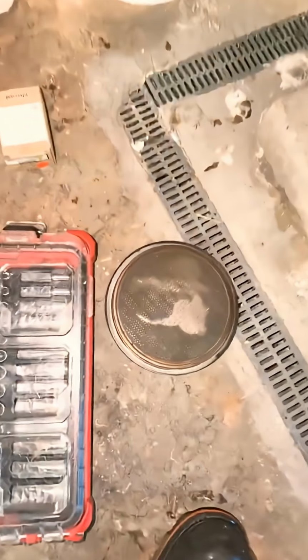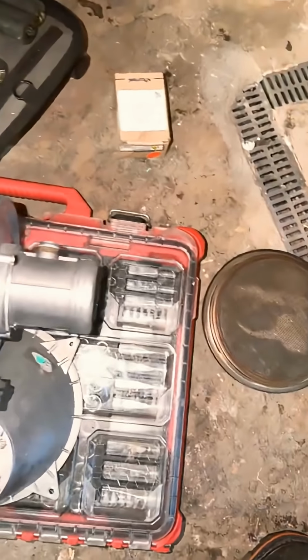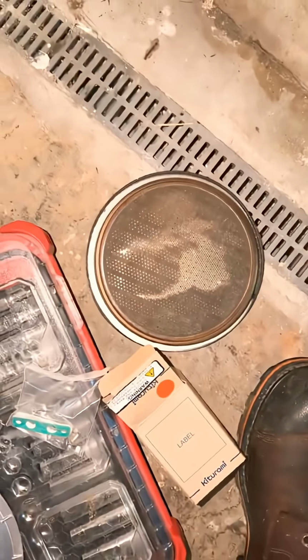But that's why maintenance is important on these. I did not want to put it back together like that. And I also have a new electrode. So these are two very common items to do on a maintenance. It would be the ignition electrode on most gas-fired boilers and furnaces, and that pad. So it might not be bad to keep one of those on your truck if you do Bradford White.